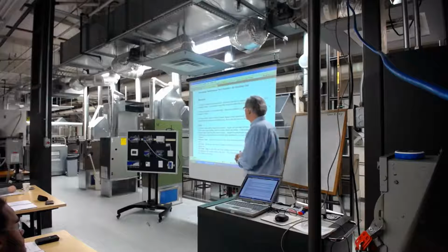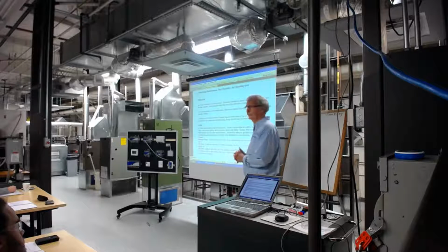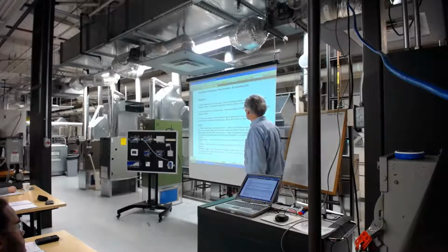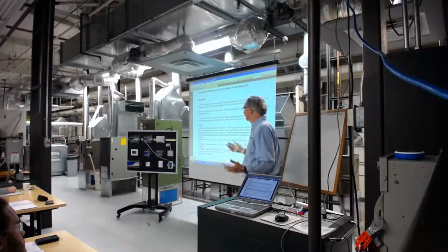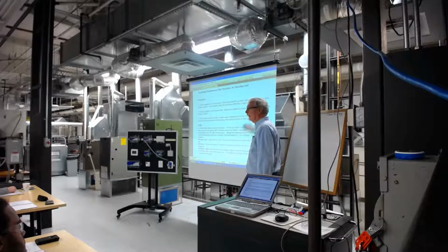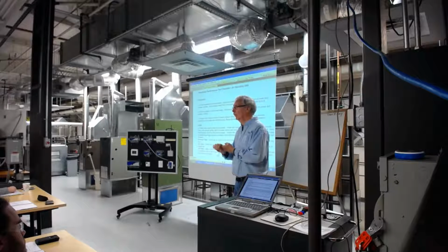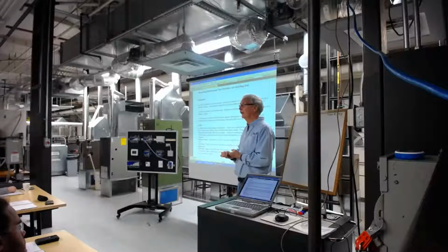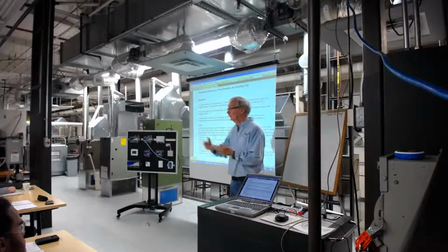Proper motor location, yeah. You've got a centrifugal fan with a wheel spinning, right? Just because it's labeled doesn't mean the motor's going that direction. So in other words, when an electrician comes in and reverses one of the phases, what happens? It goes backwards. If the motor goes backwards, will you get no flow, all the flow, or some flow of air? Yeah, you get some.